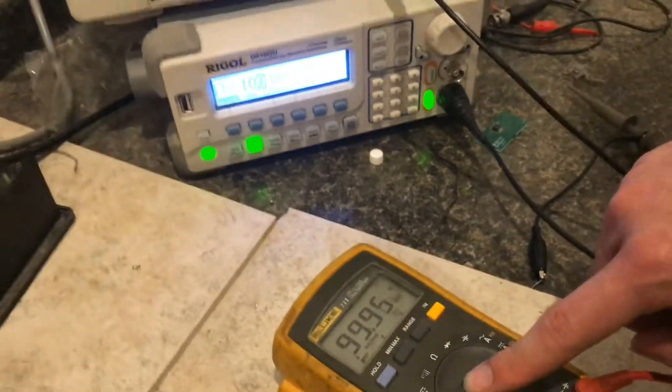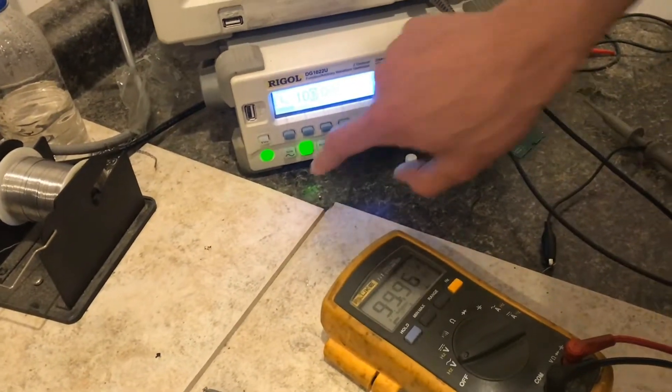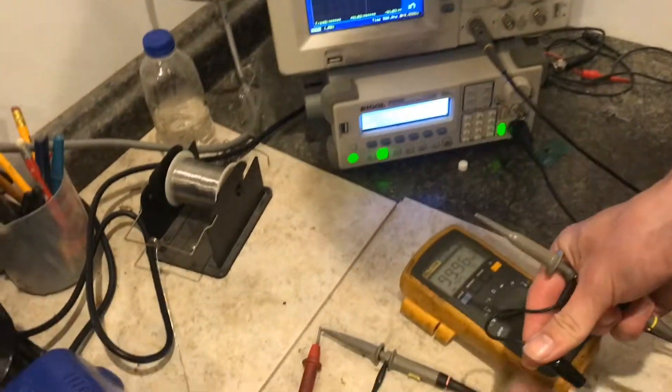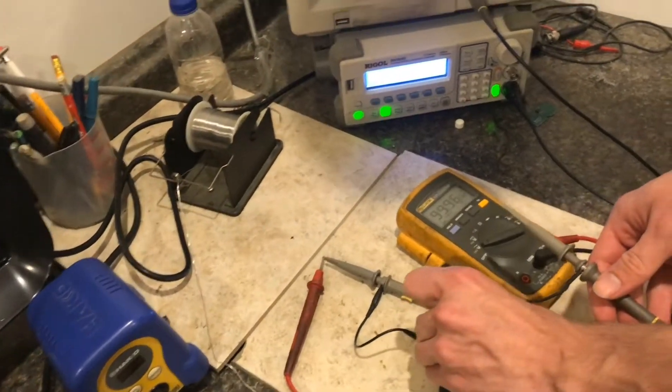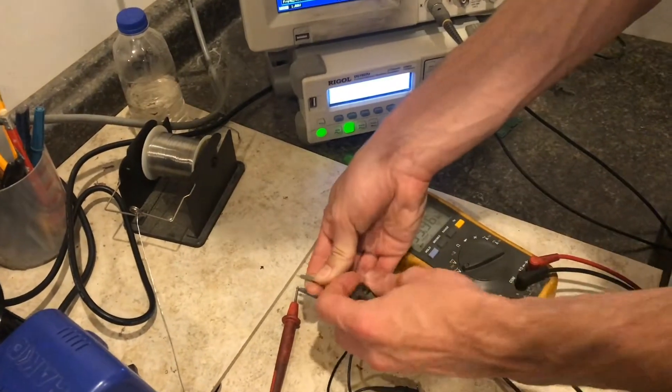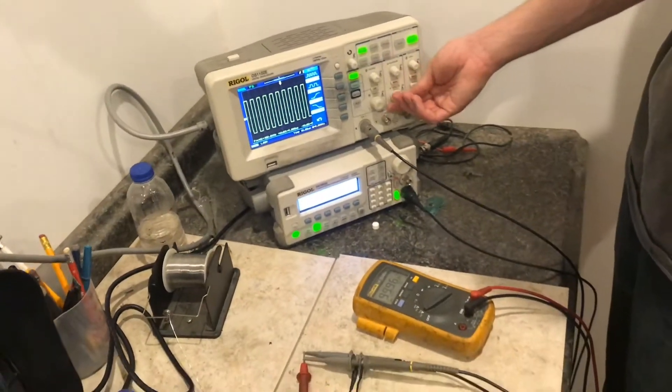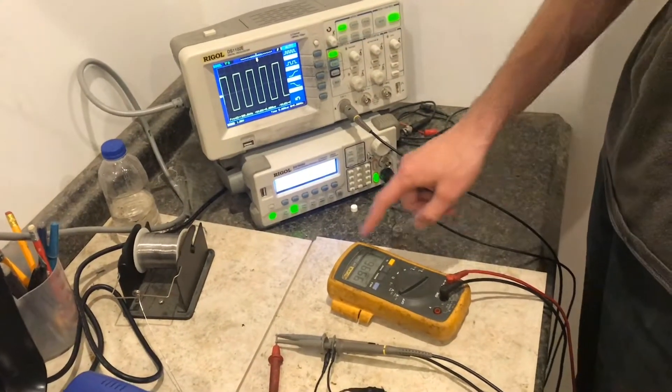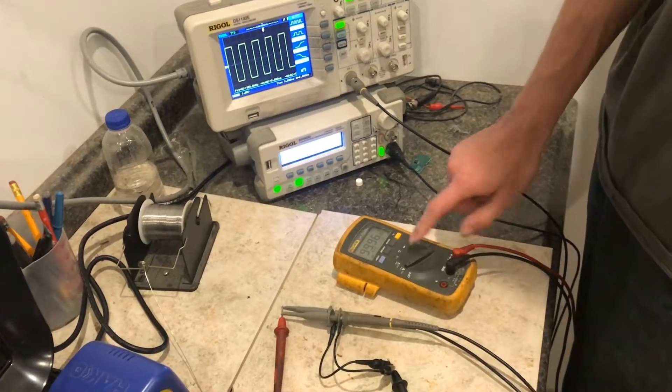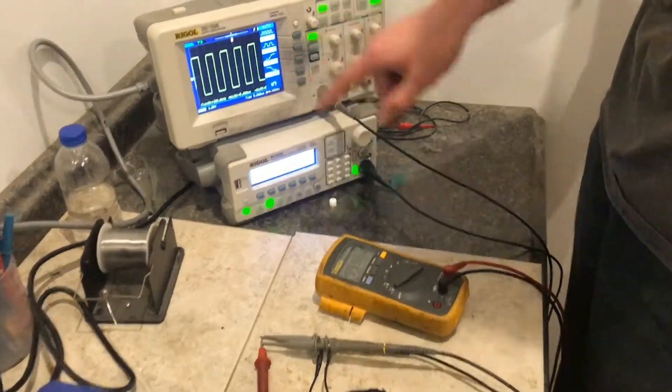So let's now see if we go to a different type of waveform. So this was a square wave, and if I hooked my oscilloscope up to the same, so we can actually measure the same signal coming from the signal generator. We just zoom out here a bit. So that's a nice-looking square wave, that's what the Fluke meter is trying to figure out the frequency of, and verify with our scope that it's 100 kilohertz.